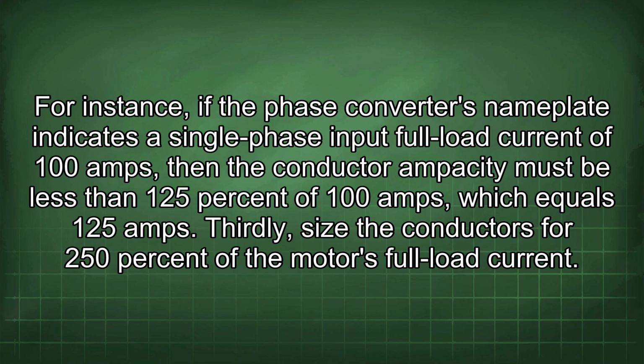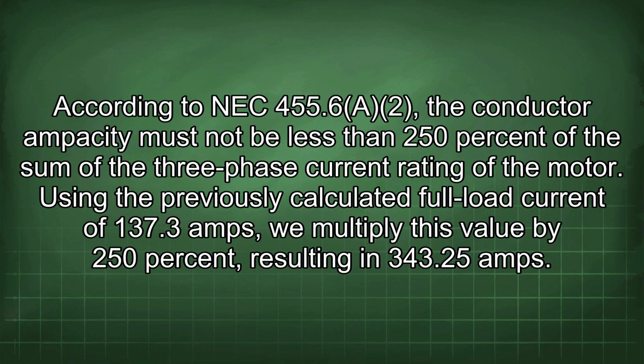Thirdly, size the conductors for 250% of the motor's full load current. According to NEC 455.6(A)(2), the conductor ampacity must not be less than 250% of the sum of the three-phase current rating of the motor.